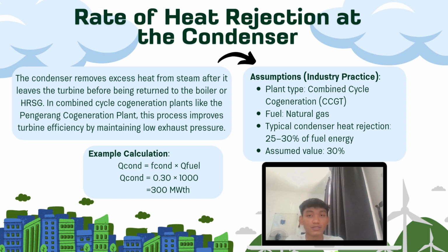Next is the rate of heat rejection at the condenser. The condenser removes excess heat from the steam after it leaves the turbine, before being returned to the boiler or HRSG. In combined cycle cogeneration plants, like the Pengerang cogeneration plant, this process improves turbine efficiency by maintaining low exhaust pressure. For the assumption, the plant type is combined cycle cogeneration, the CCGT, and the fuel is natural gas. The typical condenser heat rejection is 25% to 30% of fuel energy. The value that we use is 30%.